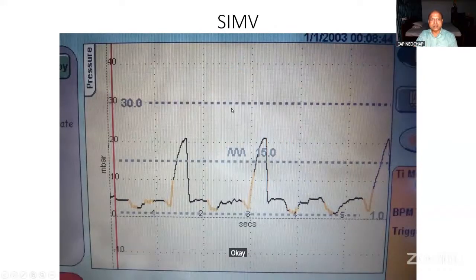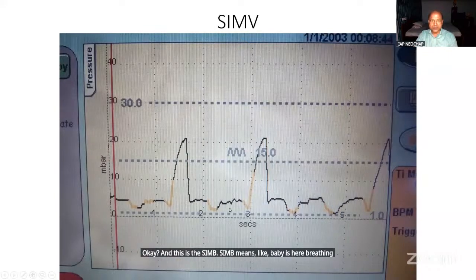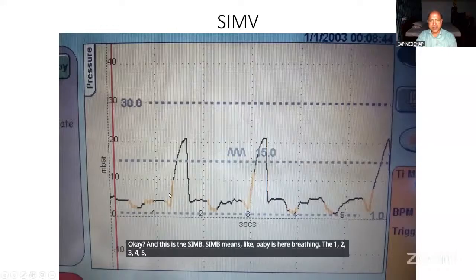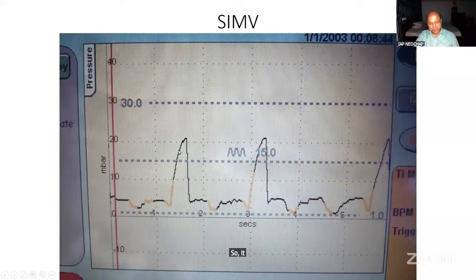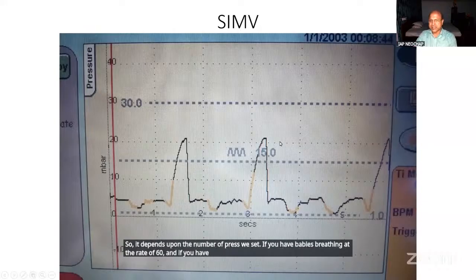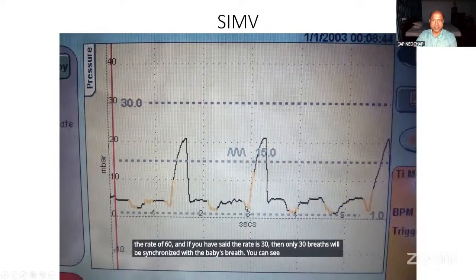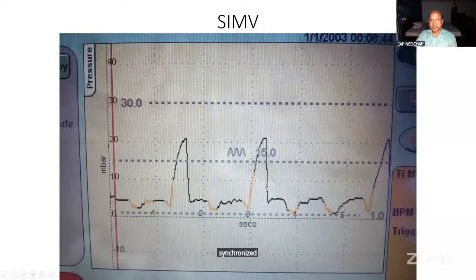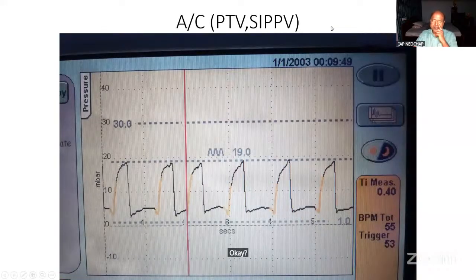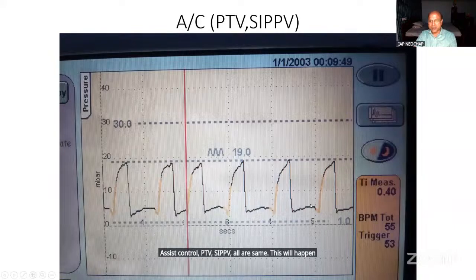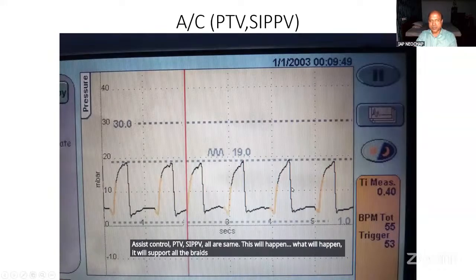Okay. And this is SIMV. SIMV means the baby is breathing here. There are 1, 2, 3, 4, 5, 6 breaths, but only 3 breaths are being supported by the ventilator. So it depends upon the number of breaths we set. If the baby is breathing at a rate of 60, and you have set the rate at 30, then only 30 breaths will be synchronized with the baby's breath. You can see here, all breaths are synchronized. Okay. Assist control, PTV, SIPPV, all are the same. It will support all the breaths.